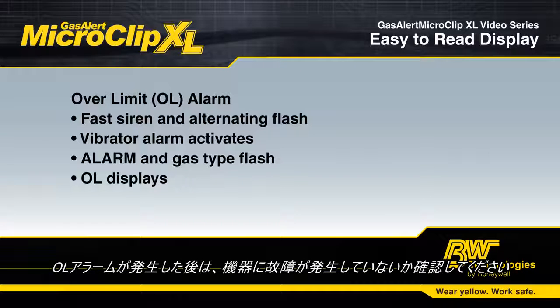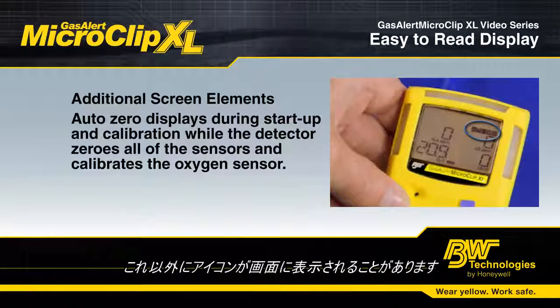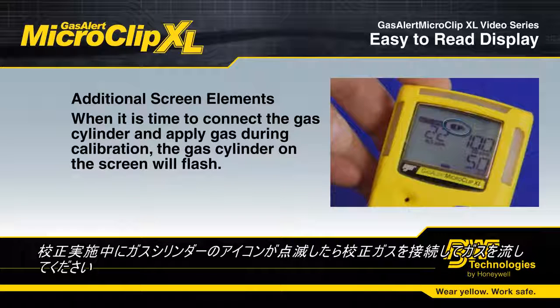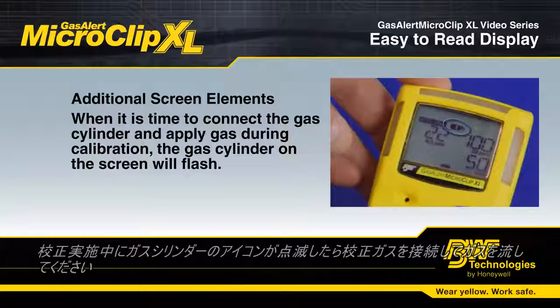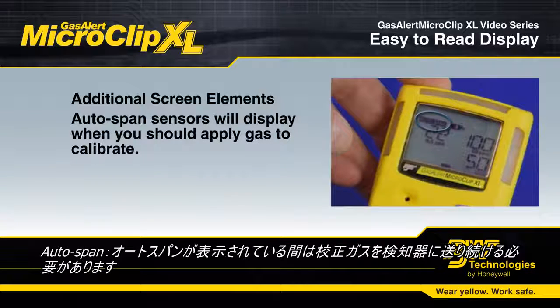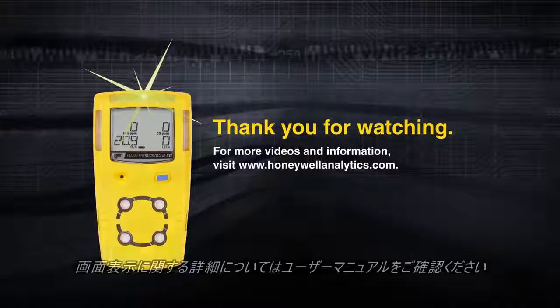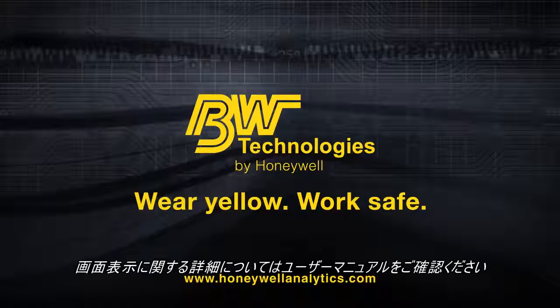Always confirm proper sensor function following an OL alarm. Other easy-to-identify icons and prompts you will see on your screen include Auto Zero, the Gas Cylinder icon, and Autospan. The GasAlert Micro Clip XL has an easy-to-read display and easy-to-interpret information. We've covered the basic elements of your screen. For more information, check out the user manual.